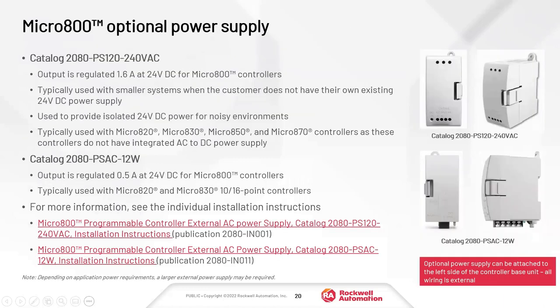The optional power supply slides onto the far left side of the CPU. The base Micro 800s all power up on 24V DC, so if your control power is 120V AC or 240V AC, you can use this optional power supply to bring AC in and output 24V DC to power your Micro 800.